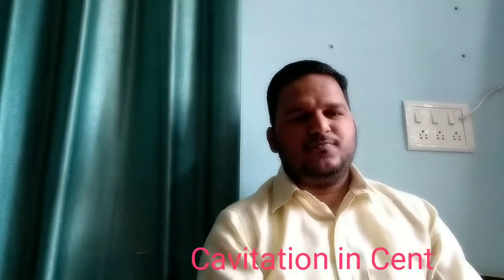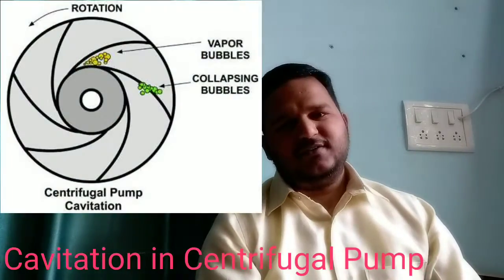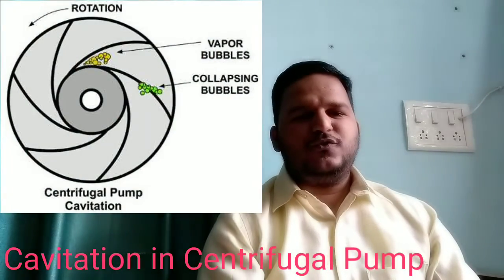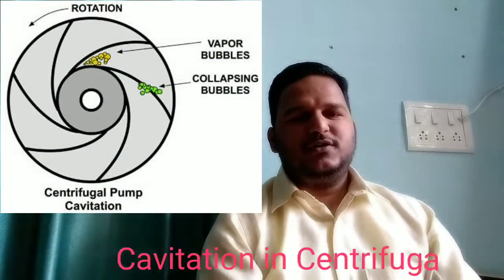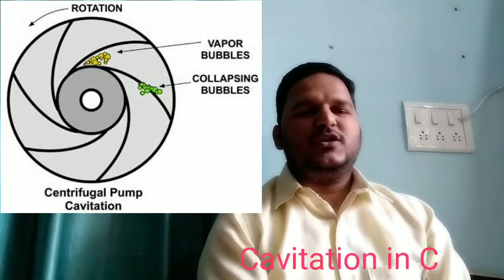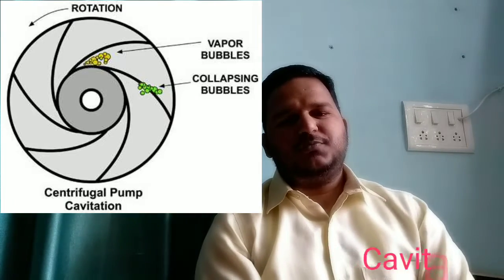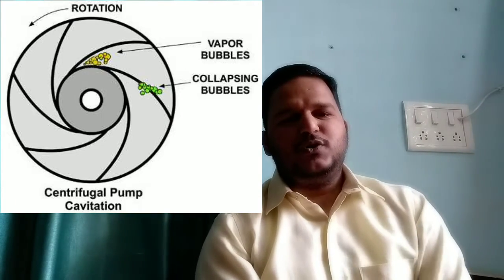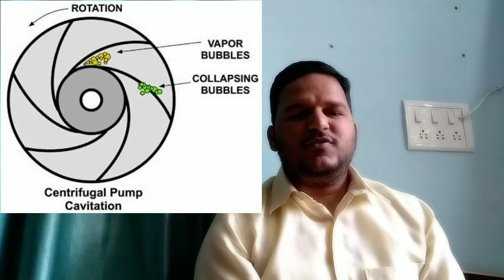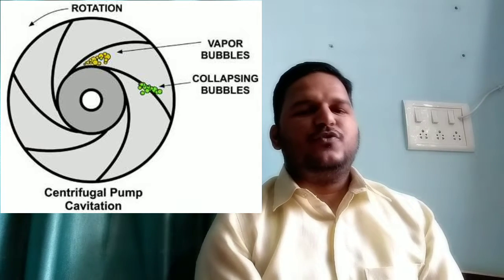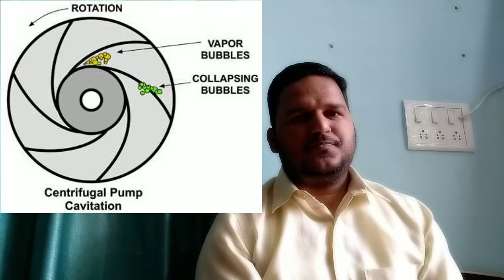Hello friends, today we are going to see cavitation in the centrifugal pump. Cavitation is defined as the phenomenon of formation of vapor bubbles in the region of flowing liquid where pressure falls below the vapor pressure of the liquid. Then the liquid will vaporize and flow will no longer be continuous.